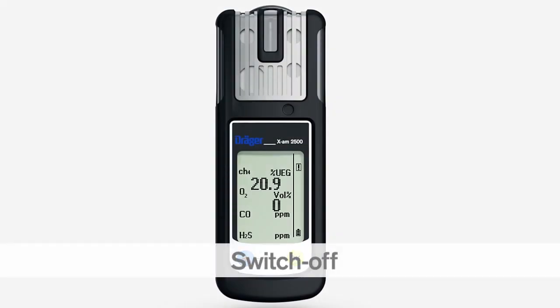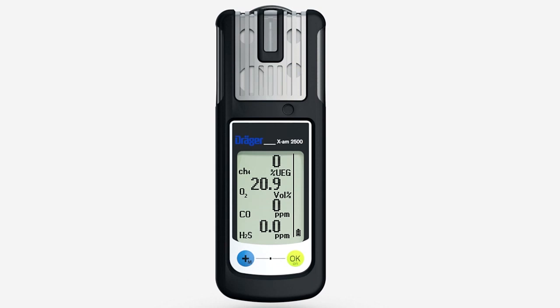To switch off the Dräger X-am 2500, press and hold the OK key and the plus key together for 3 seconds. The visual alarm flashes and the audible alarm beeps to indicate that the shutdown sequence is complete.